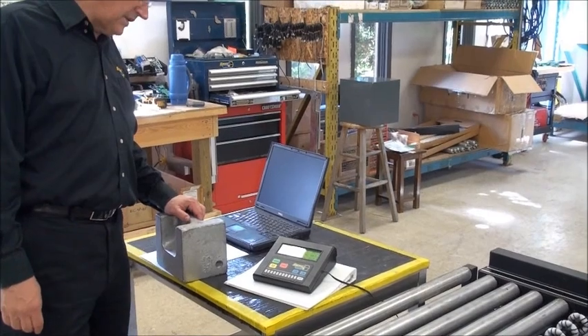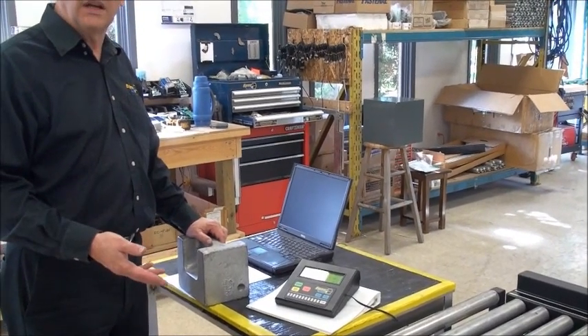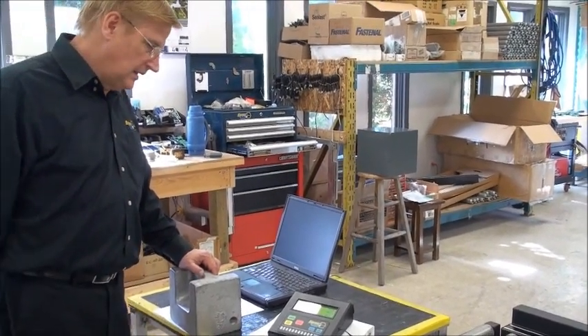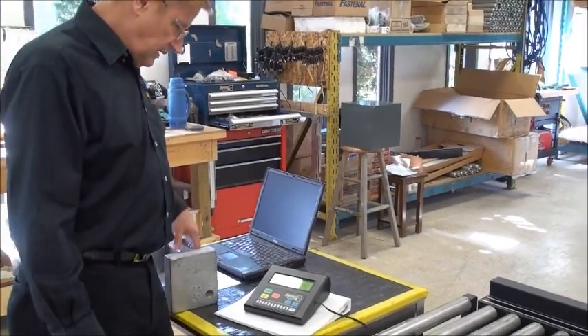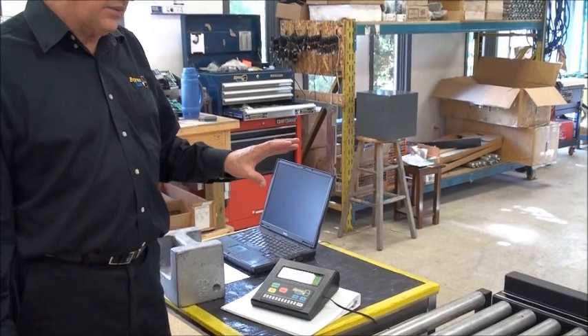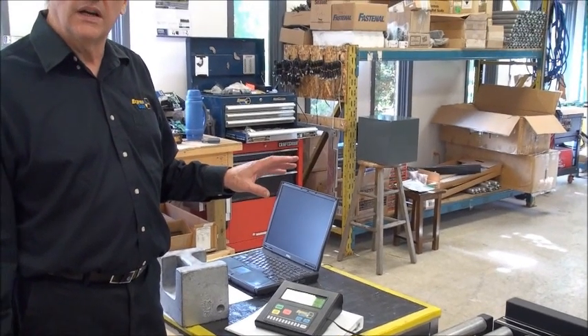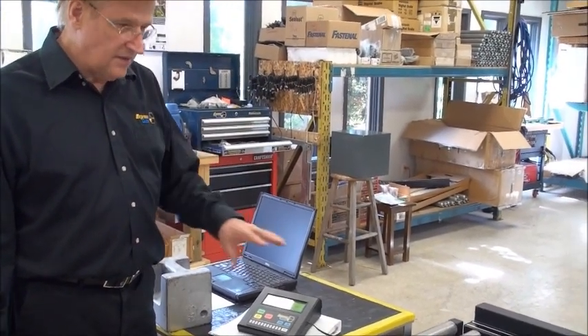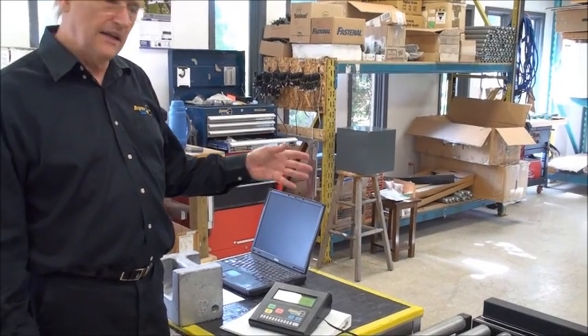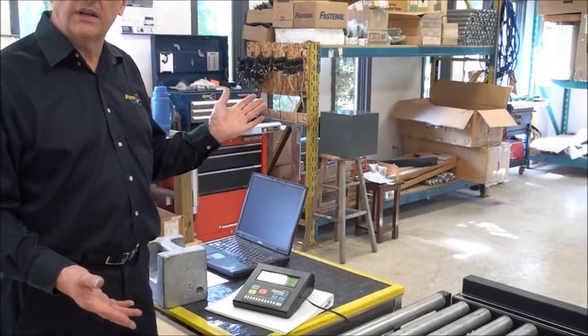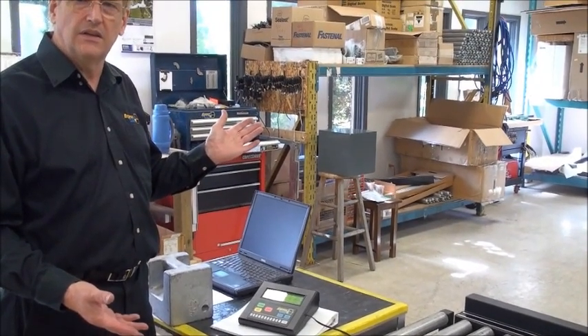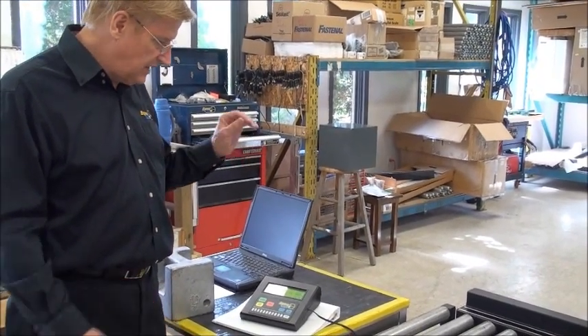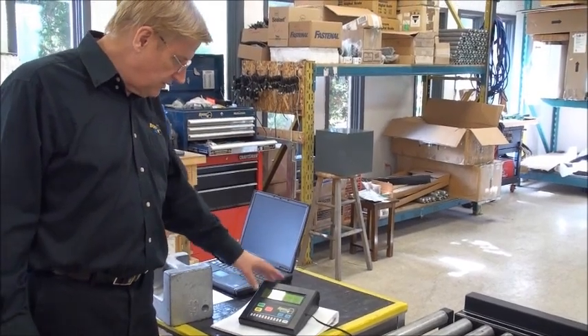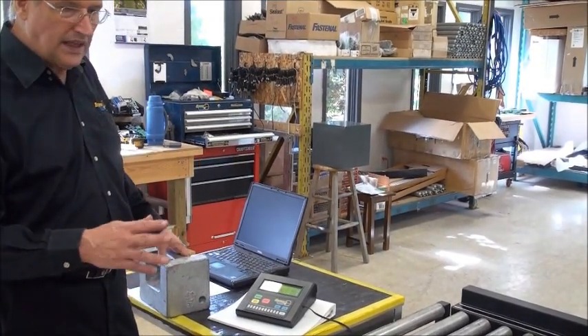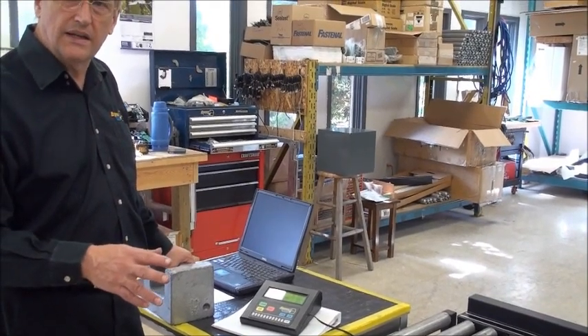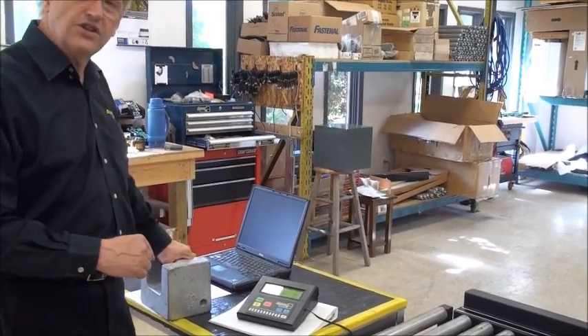All right, now what we're going to do is just review how to do calibration on the 480. A couple things. When we calibrate it at the factory, we are using 100 pounds, and you may not have 100 pounds ready, or if you're in metric, you may have 25 kilos or 50 kilos or whatever. So I'm going to show you on here how to verify what the current calibration weight is on the machine and how to change it.